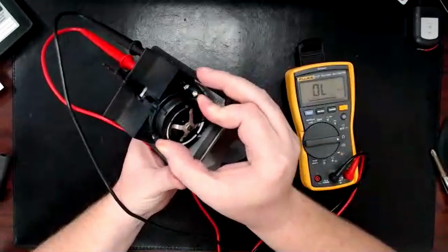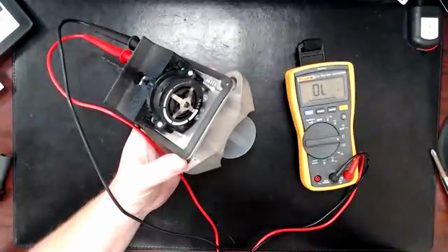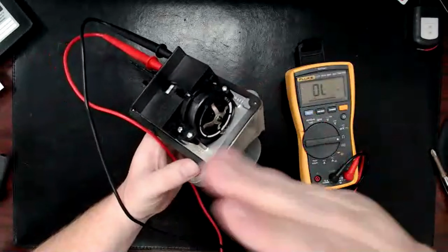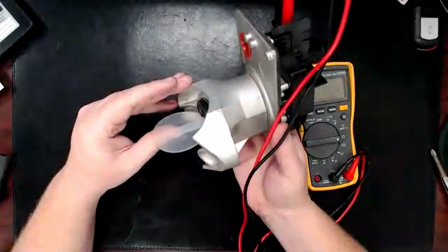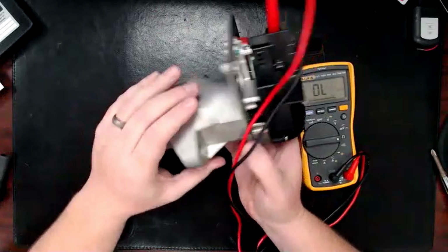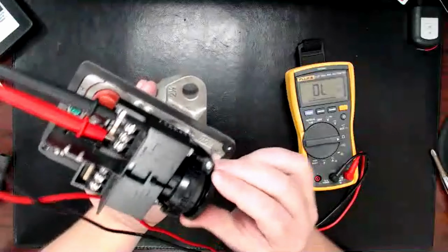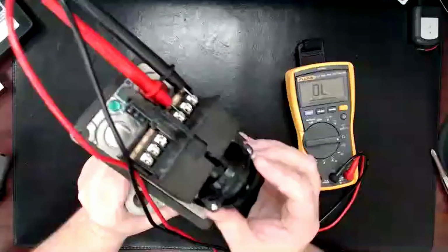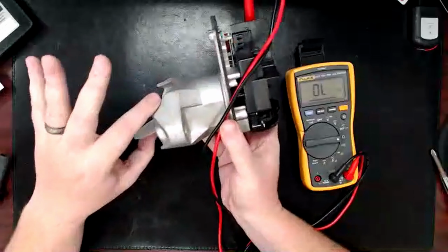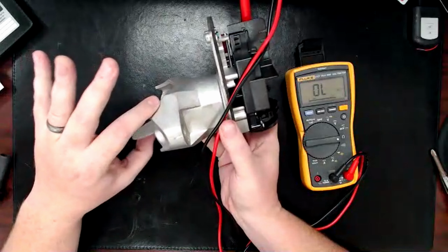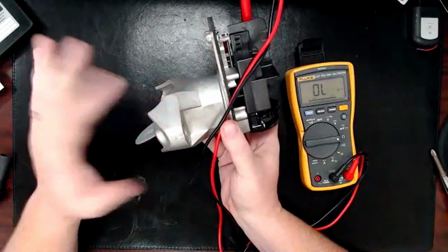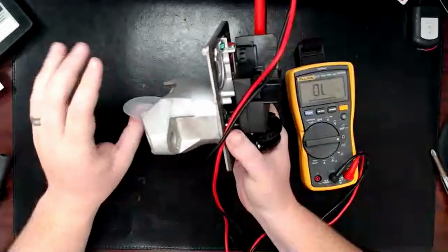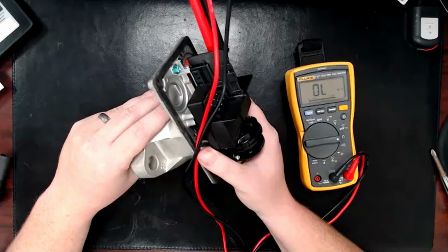So you can adjust that delay so that as the water pressure fluctuates up and down, it won't set the alarm off. It'll let the water pressure move so that this switch kind of goes back and forth a little bit flowing with water, but it won't actually set it. So instead, if you were watching right there when I was doing that, you could see that it went into alarm just as soon as I touched it and started moving it. And if I set that timer right here, that allows pressure to build back up and it moves the paddle and then it stops and returns, and it never went into alarm. But you can set it short enough so that if water is actually flowing, there's just a little bit of a delay and then it'll switch into alarm.